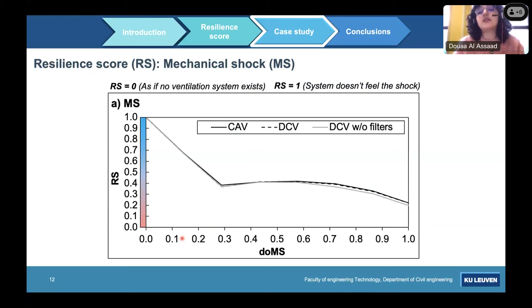Now I will also show you the results of the internal disruption. This is for a maximum internal disruption for CAV, DCV, and DCV without filters. With CO2, we noticed that the CAV has better absorptivity and faster recovery than the DCV. This can be due to the fact that with demand control ventilation, we have a response time that is slower than the CAV, which is why we see this behavior.